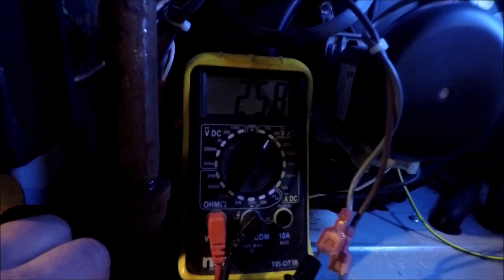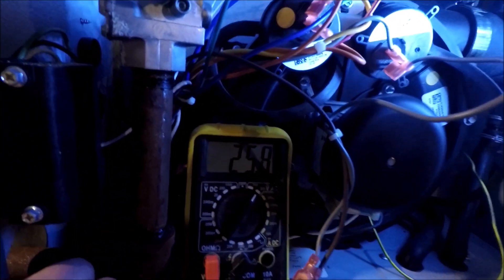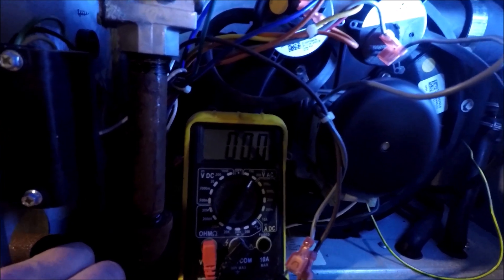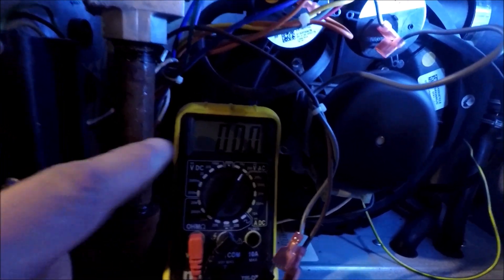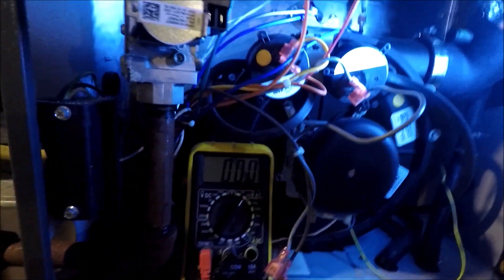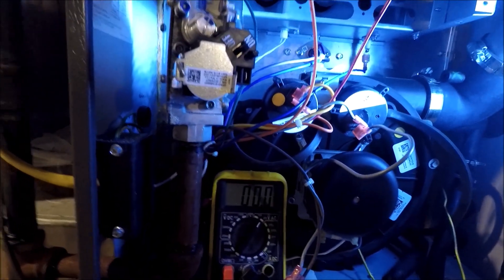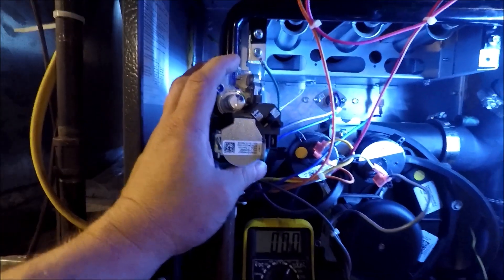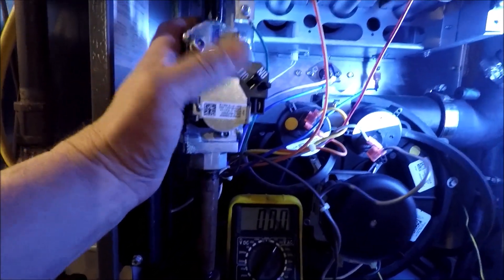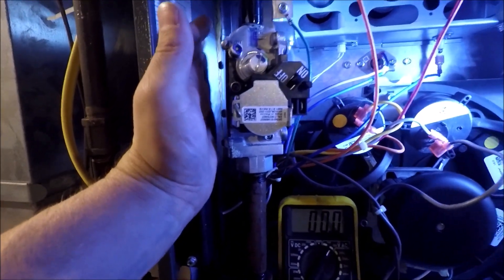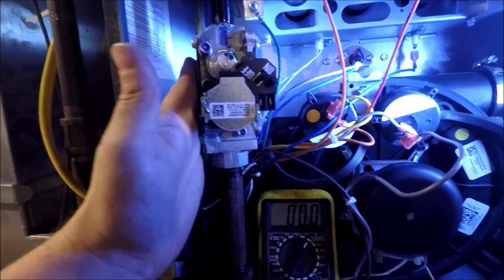There's a reflection of the voltage. So I know that I have, let me stay on for a second here. I know that I have voltage to my gas valve here and it is on, I'm on the on position. So I know I'm getting voltage.